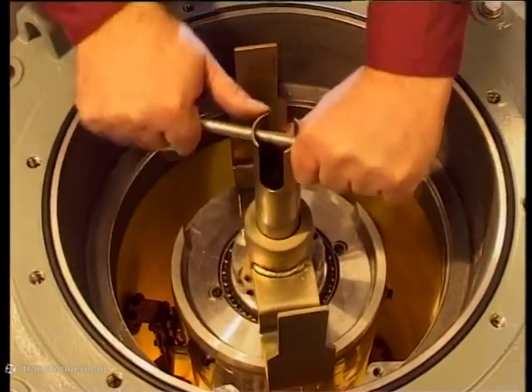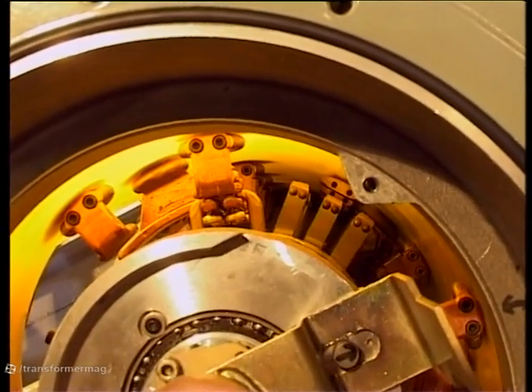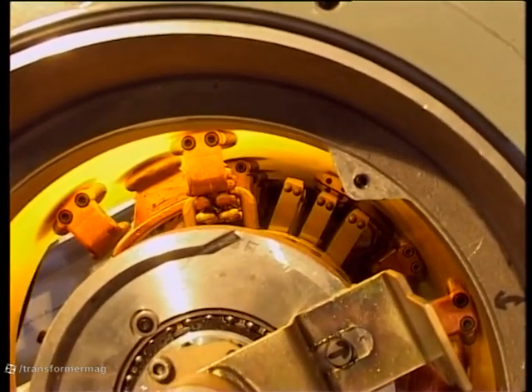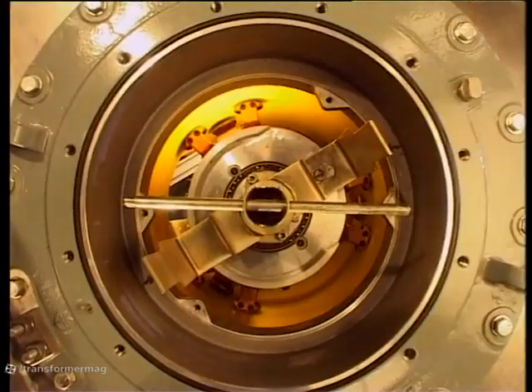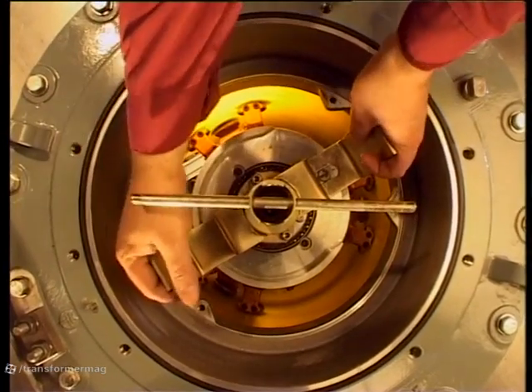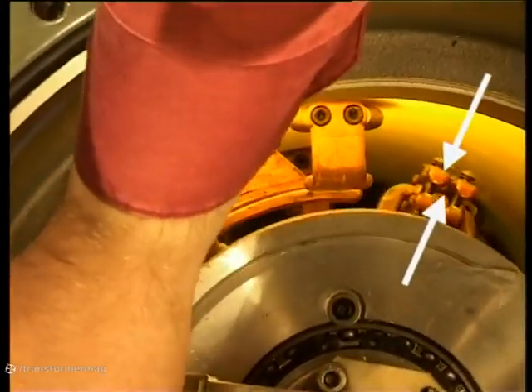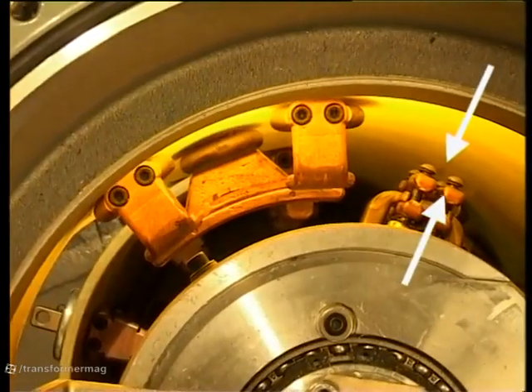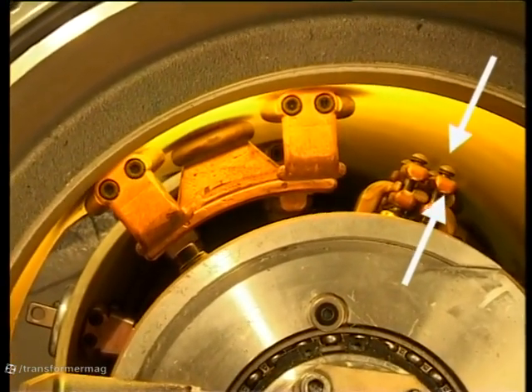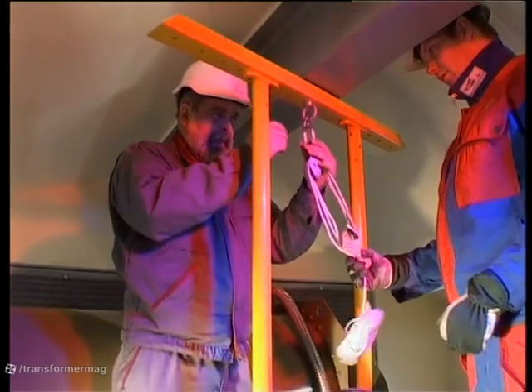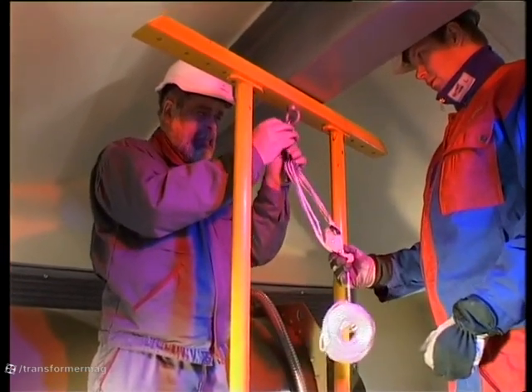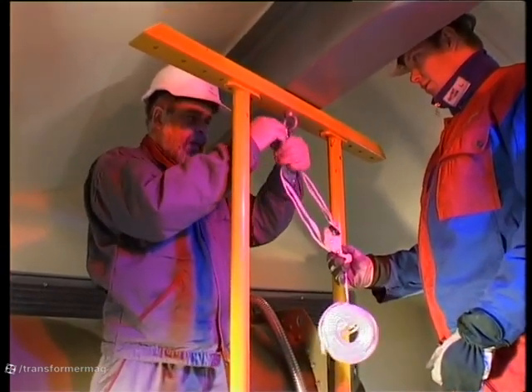Turn the tool until the moving contacts of the selector switch reach the position of the fixed contacts that you removed. Using the arm, turn the moving contacts of the changeover selector until they're between two fixed long contact blades. The moving assembly weighs about 30 kilos. Use a block and tackle to lift it.